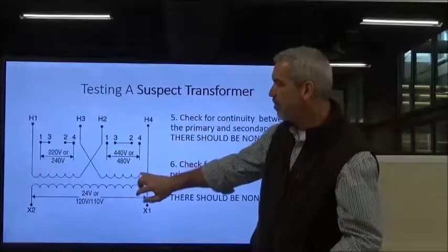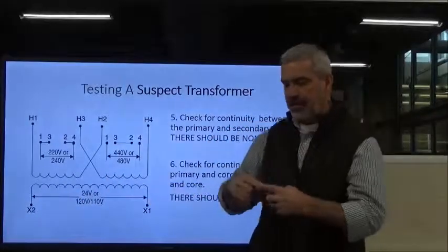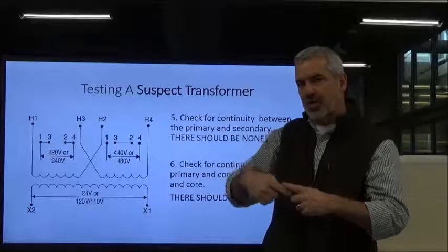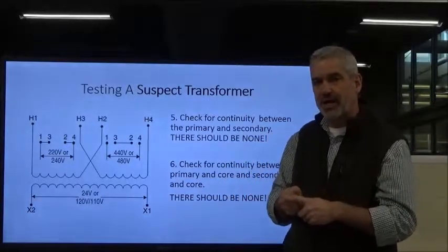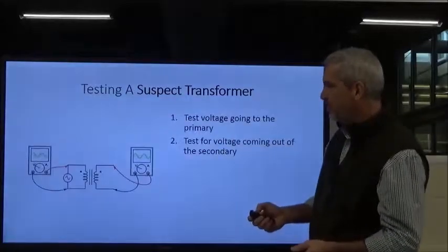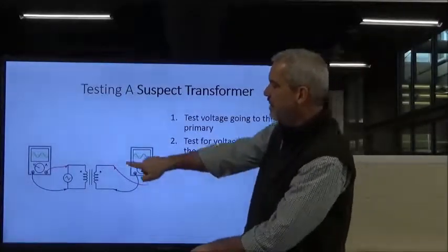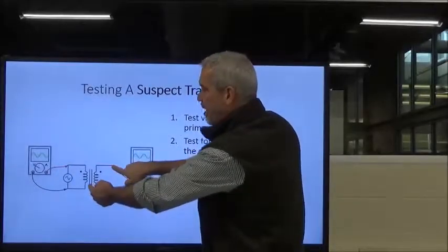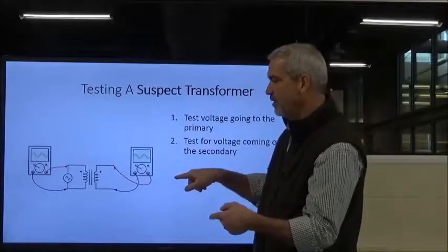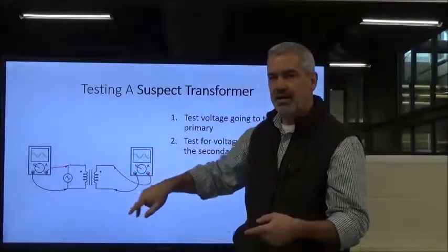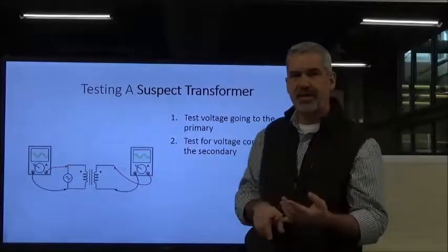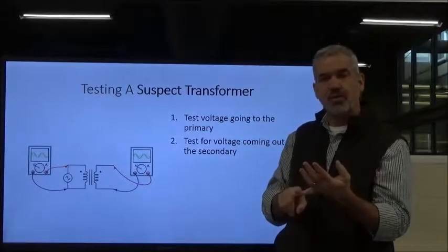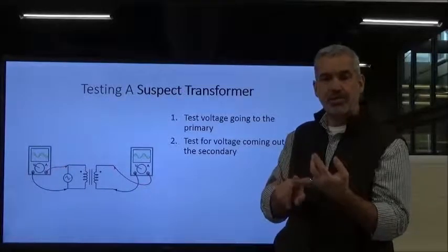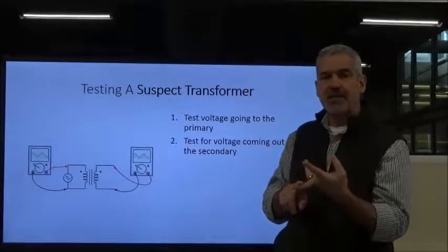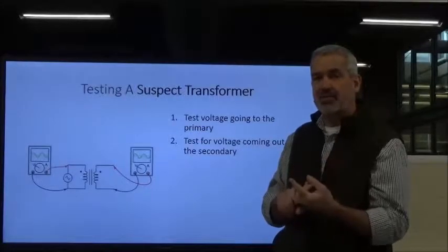And likewise, you should not have any type of continuity between your coils and your core. Again, the coils are wrapped around that iron core, and with vibration and everything, they could possibly short to the iron core. So let's see if I can get a picture here. What we would do is check with our meter, literally putting it on the outside of the iron core, making sure you have a good connection, to make sure the primary and the secondary are not touching that iron core. Those are the three ways they can fail. One of the coils can short out, one of the coils can burn open, or the coils could possibly come in contact with the iron core. That's the way they fail.